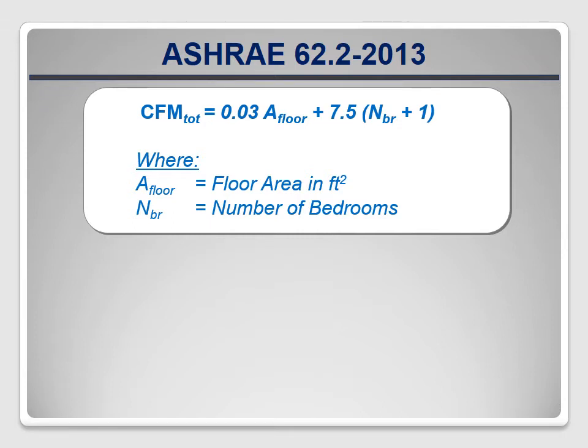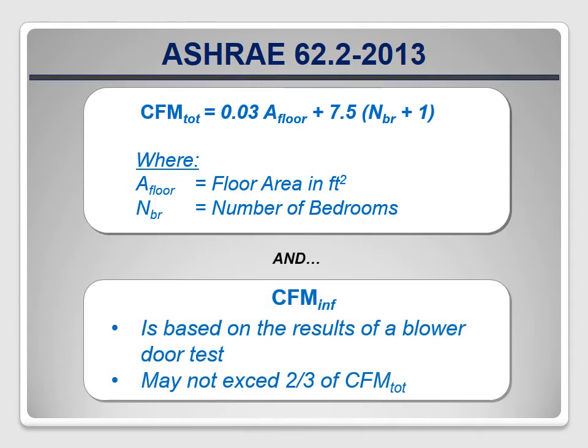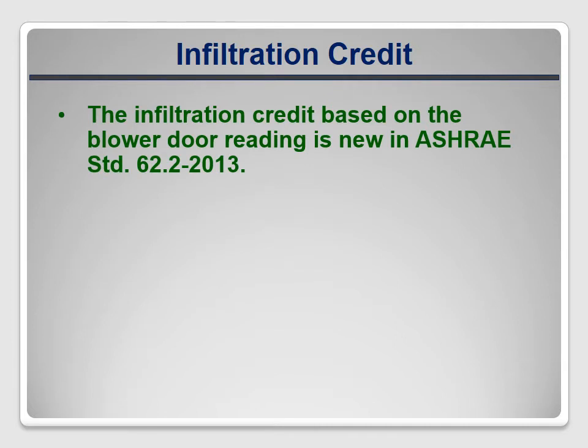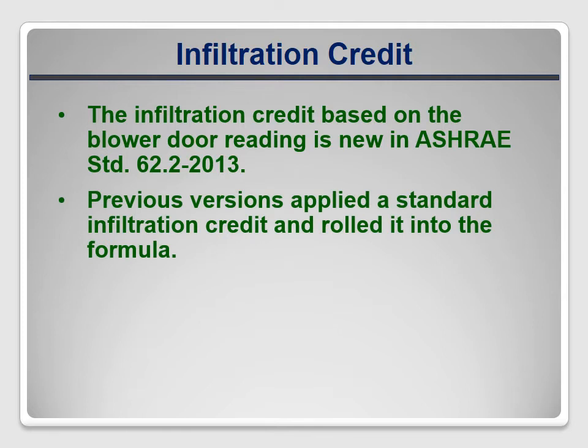The CFM infiltration, which is called the infiltration credit in the standard, is determined based on a blower door test on the completed house and it cannot exceed two-thirds of the CFM total. This method of using the blower door reading to determine an infiltration credit specific to each house is new to the 2013 version of ASHRAE 62.2. Recent versions applied a standard infiltration credit to each house and rolled it into the formula. In the 2007 and 2010 versions, for example, the credit was 2 CFM per 100 square feet of floor area.